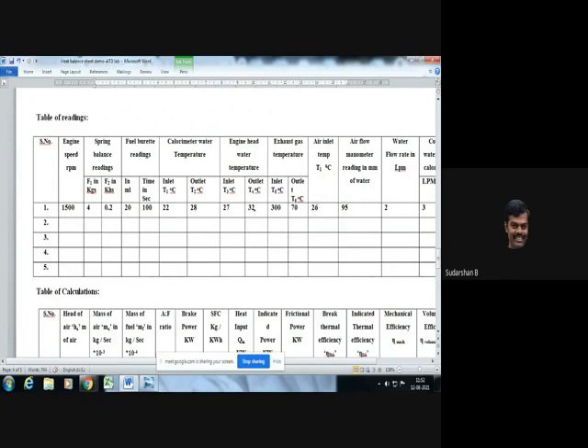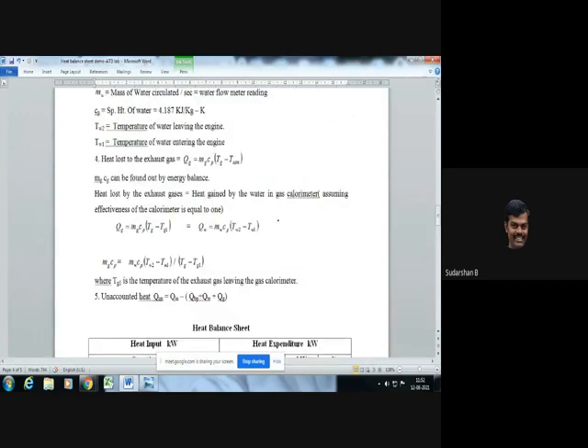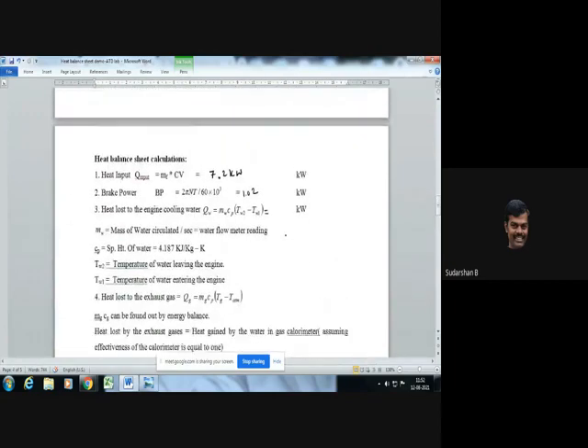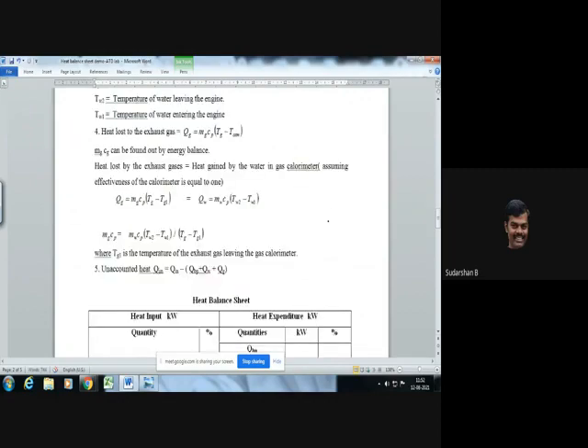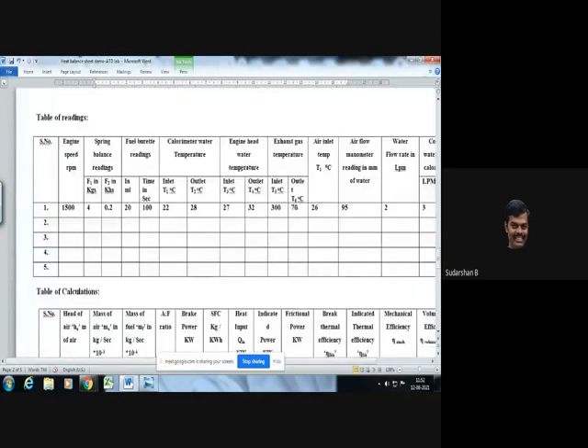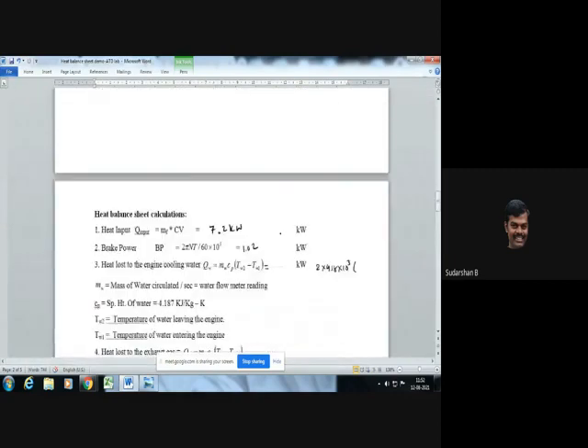Then take delta T, Cp is 4.18. Let's see that now, 2 liters per minute, you have to convert this. Cp is 4.18 into 10 raised to 3, specific heat of water. Tw2 minus Tw1 is 32 minus 27. So this you have to convert in terms of meter cube per second.